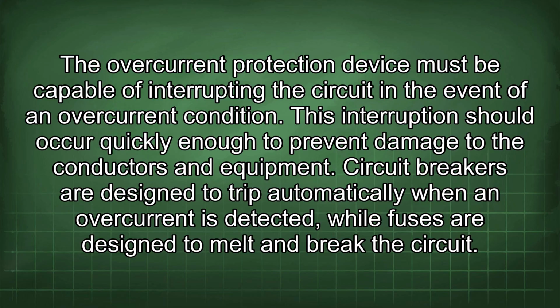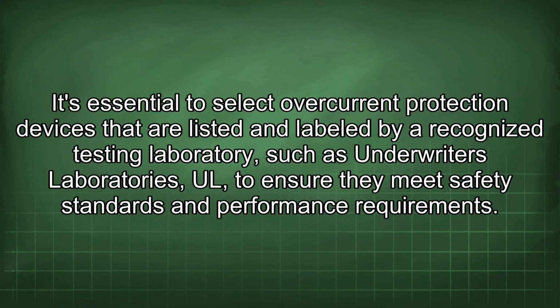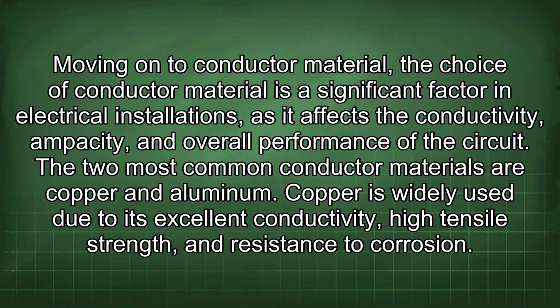Circuit breakers are designed to trip automatically when an overcurrent is detected, while fuses are designed to melt and break the circuit. It is essential to select overcurrent protection devices that are listed and labeled by a recognized testing laboratory, such as Underwriters Laboratories, UL, to ensure they meet safety standards and performance requirements. Moving on to conductor material.